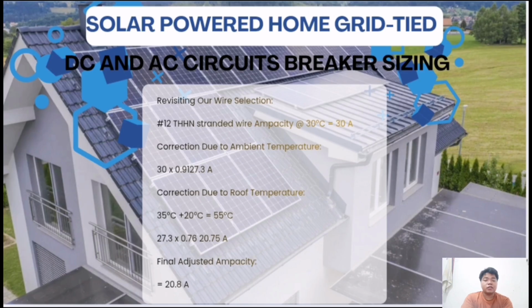Pero sa actual setup, hindi naman lagi ganun ang environment, kaya kailangan natin ng adjustment o tinatawag na derating. Una, meron tayong ambient temperature correction. Dahil sa mainit sa actual environment kaysa sa standard, bumababa yung capacity ng wire. Kaya imbes na 30 amperes, i-multiply natin siya sa 0.91. 30 times 0.91 equals to 27.3 amperes. Ibig sabihin, dahil sa init ng paligid, naging 27.3 amperes na lang yung safety capacity niya.